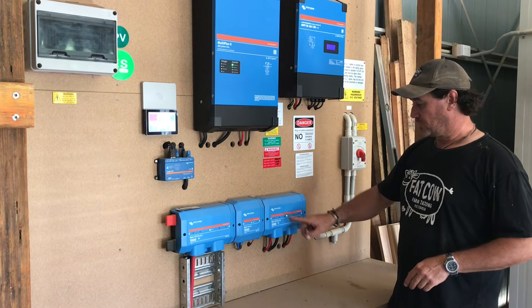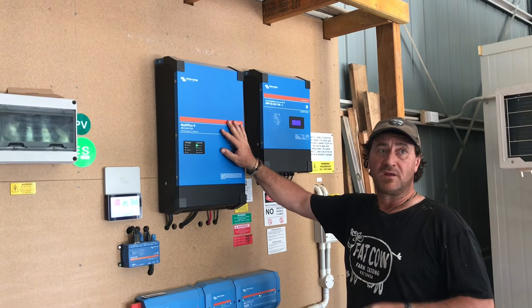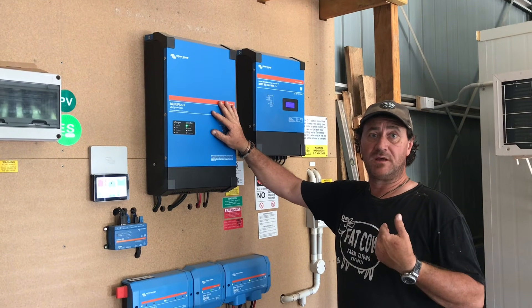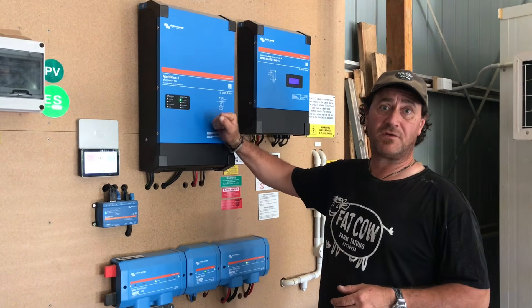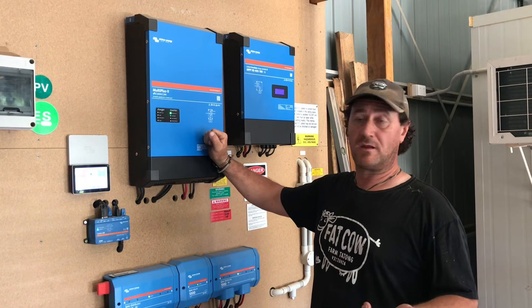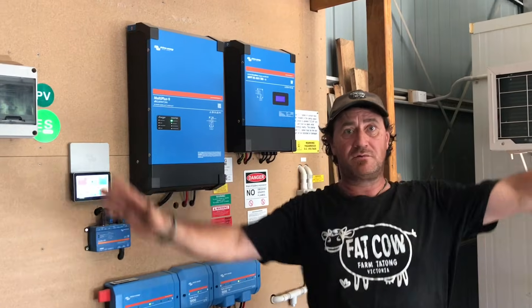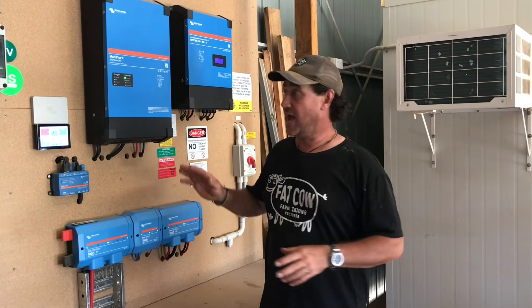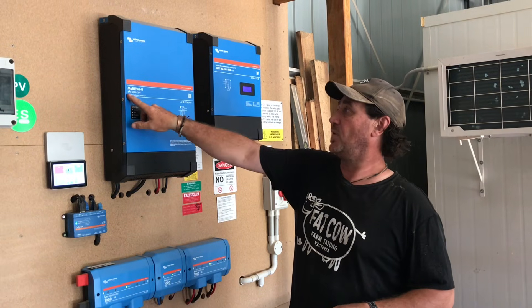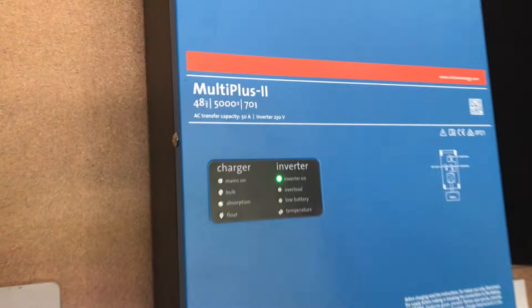Then what happens is it comes back to the Lynx Distributor and up to the inverter. This is the inverter which converts the voltage. We've got a 48 volt system here, so this will convert the 48 volts into your standard Australian 240. From here it then goes to the switchboard, and from the switchboard it's distributed through the shed, cool room, normal power outlets, lighting circuits and things like that. We have the 48 volt 5000 watt 70 amp unit — that's our inverter.